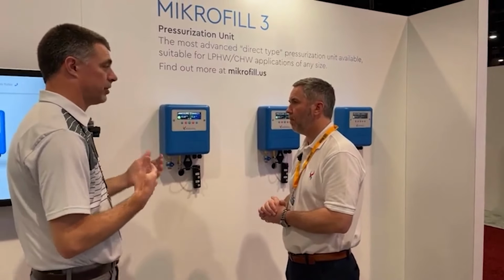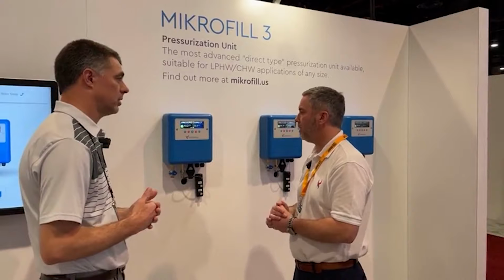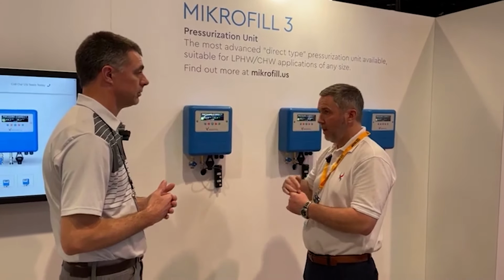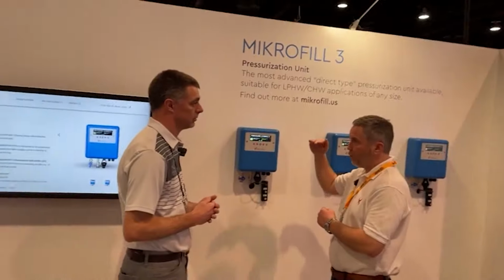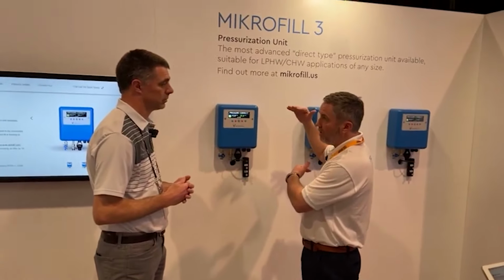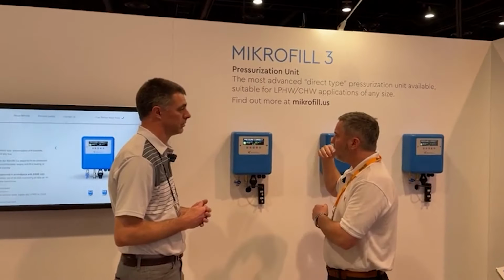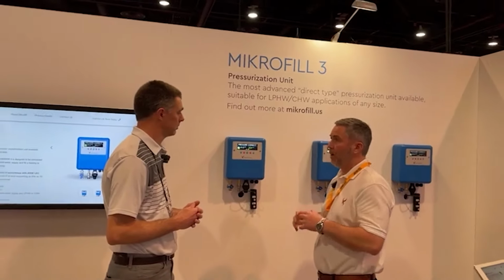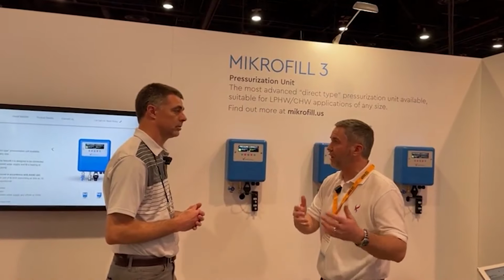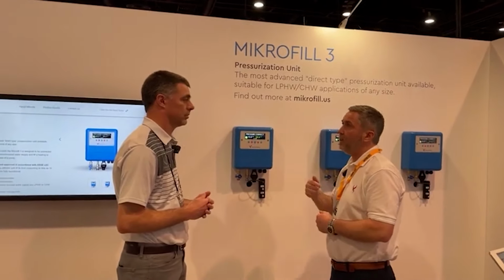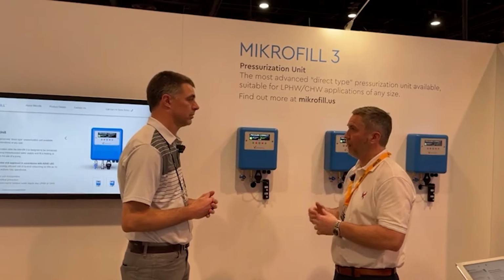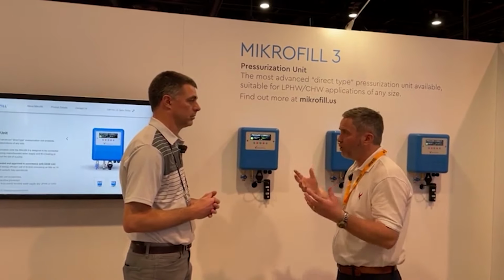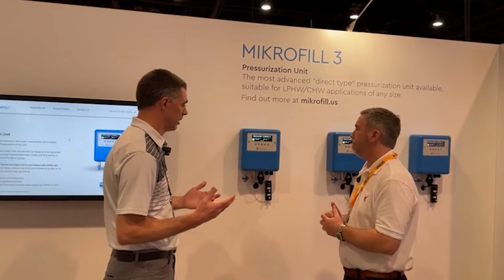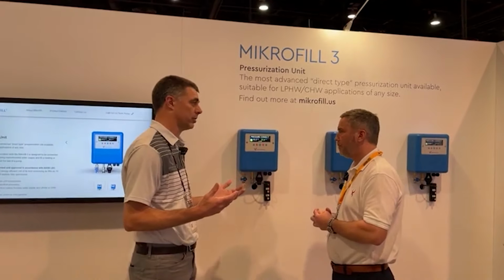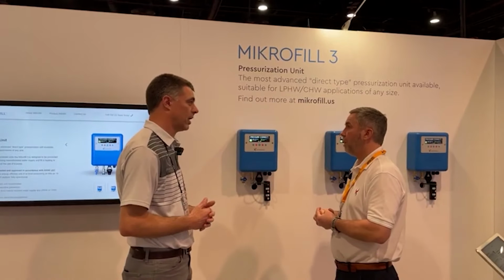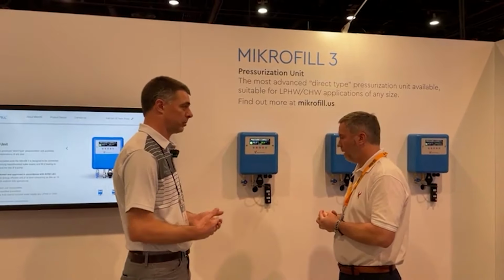So does this offer any monitoring and alarms out to a customer? Yes, it does. At the moment it's on BMS, so we've got high level and low level. They're relative to the cold fill setting, and of course they're changing and movable, relative to the P&T valve on a heating circuit or otherwise. So what it's doing really is protecting the capital plants. If you have a large chiller or expensive boiler plant, hundreds of thousands of dollars, you put this on the wall, and it's going to monitor that. It's going to protect it from low level and high level, to prevent it from potentially running dry or overpressurizing, cracking, etc. That's fantastic, because if we run dry or crack one of those systems, that costs, as you said, hundreds of thousands of dollars sometimes in repairs or downtime, lost manufacturing, who knows.